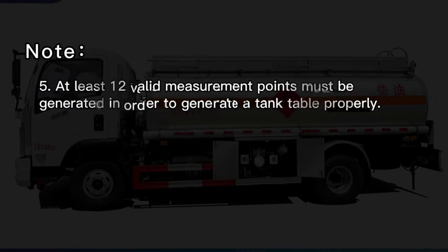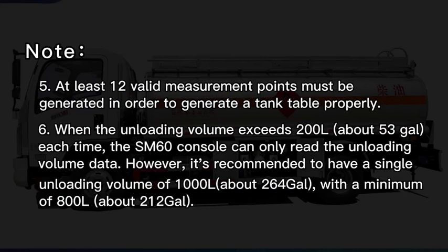5. At least 12 valid measurement points must be generated in order to generate a tank table properly. 6. When the unloading volume exceeds 200 liters, about 53 gal each time, the SM60 console can only read the unloading volume data. However, it's recommended to have a single unloading volume of 1000 liters, about 264 gal, with a minimum of 800 liters, about 212 gal.